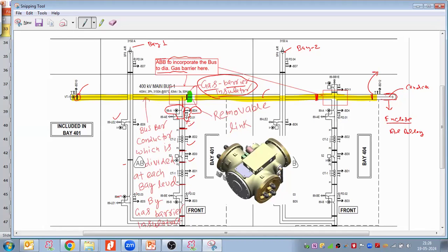As a designer, you have to ensure that they have provided the correct location for the gas barrier insulator. This is your first review point. Second review point, each portion must have the fittings. Third review point, they will furnish one table in which they mention the total quantity of the fittings. That total quantity should match with your SLD as well.